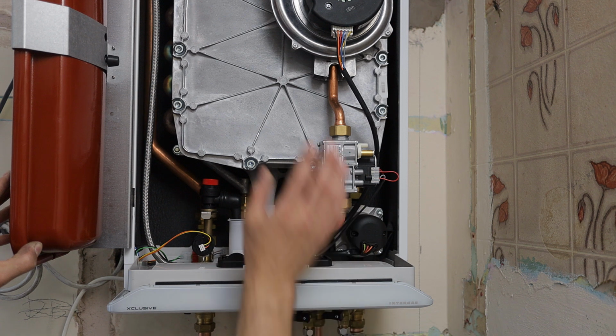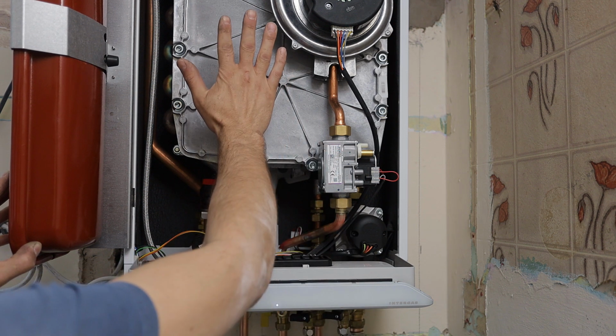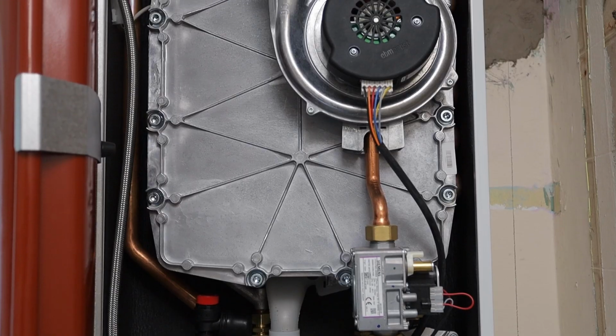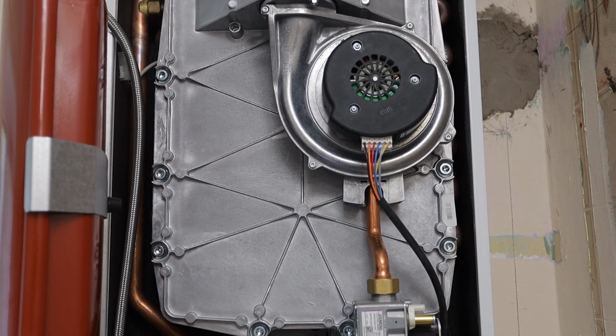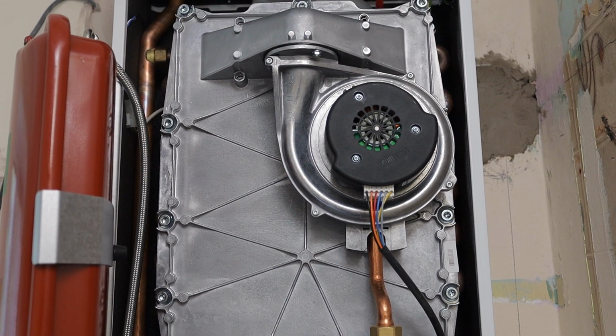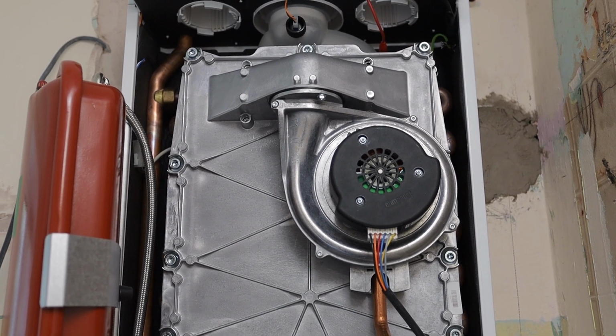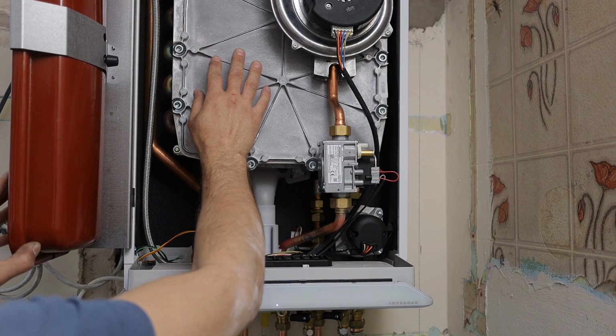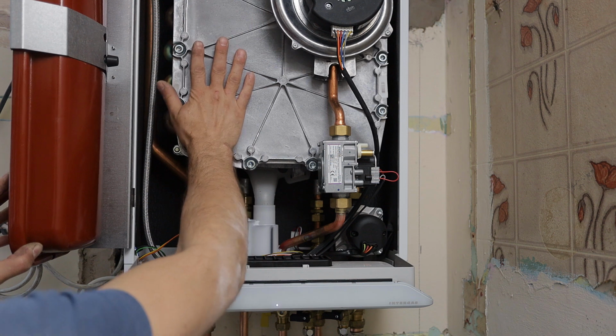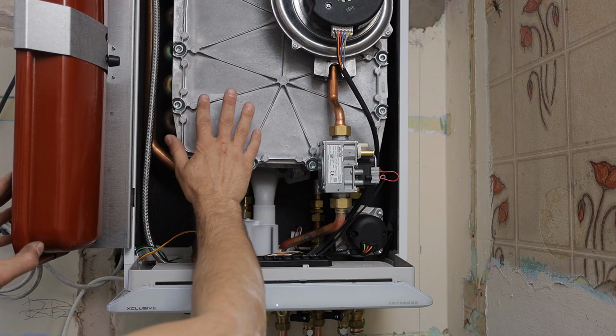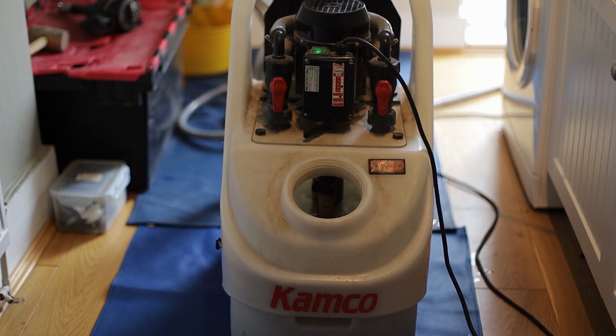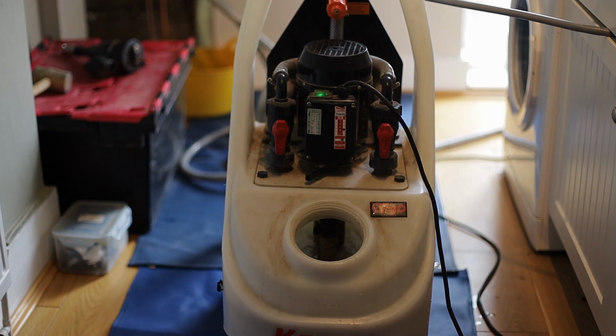That's simple. And also this is an aluminium heat exchanger on the gas side, but inside you've got copper pipework, so it's not 100% aluminium. The system water is separated by copper, so you don't have to worry about aluminium corrosion, and you can use strong chemicals to power flush systems with the boiler connected without having to worry that you will damage the heat exchanger.